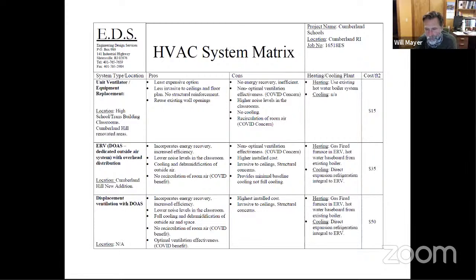Now, it is not air conditioning though - that's why we say it provides minimal baseline cooling, not full cooling. Basically just the fresh air, which is about 20 to 25% of what you'd actually need for full cooling, is treated by a refrigeration circuit in the energy recovery ventilator, so you're not bringing in hot, humid air. That does help mitigate some issues on a hot day, but certainly not full cooling.